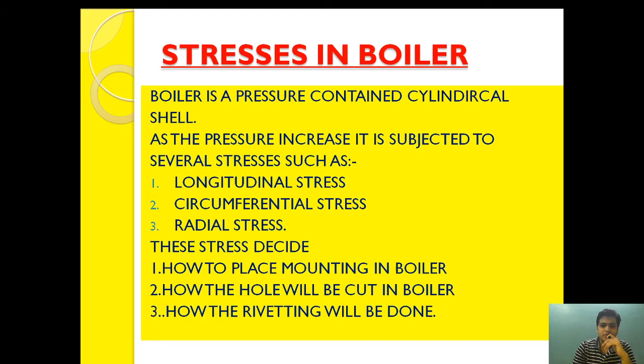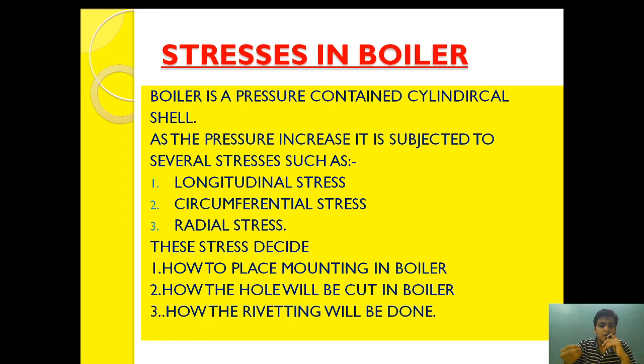These three stresses decide how holes will be cut in the boiler. We require several holes to be cut in a boiler cylindrical vessel to ensure several mountings can be installed, such as the feed water valve, safety valve, steam stop valve — many mountings and holes need to be cut so that they can be installed in a boiler. Also, how the riveting needs to be done, to ensure that the part subjected to higher stress can be additionally riveted so that it may have good structural strength. So all of this is dependent on these three stresses: longitudinal, circumferential, and radial.